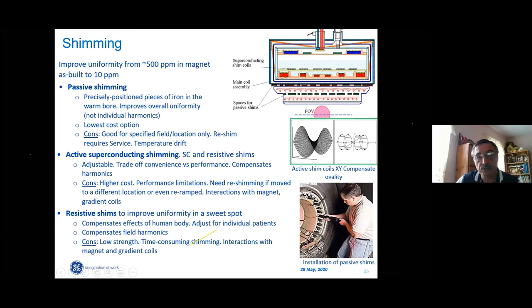Hospitals like active superconducting shimming, where they use small superconducting coils located here to improve the magnet uniformity. Physicists, especially research physicists, have better capability to control field uniformity. But it is definitely significantly higher cost. There are multiple issues to be addressed, including interaction with the magnet components, in particular gradient coils. Sometimes we also use so-called resistive shims, especially for brain imaging, when these resistive shims are installed inside the gradient coils. We just improve uniformity in a specific location, such as the nose. This is an automated procedure. So multiple techniques are possible. Let's try to find the best compromise.